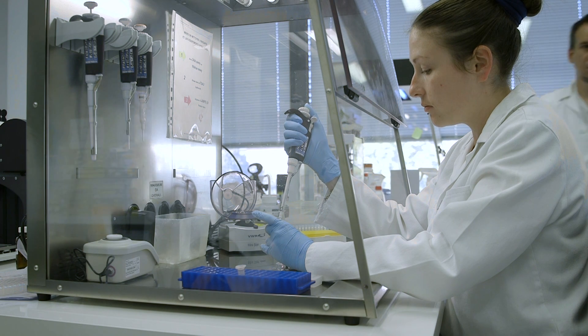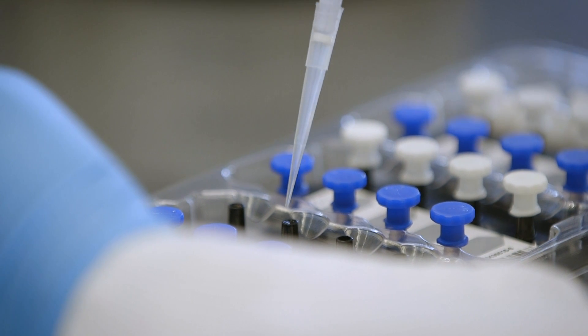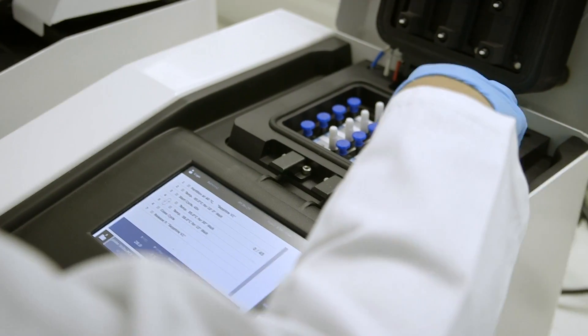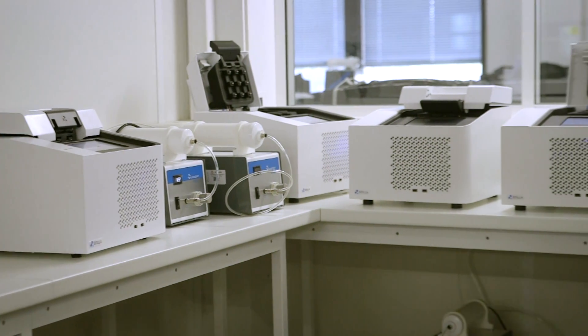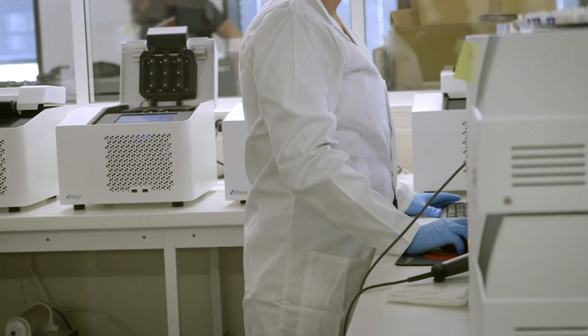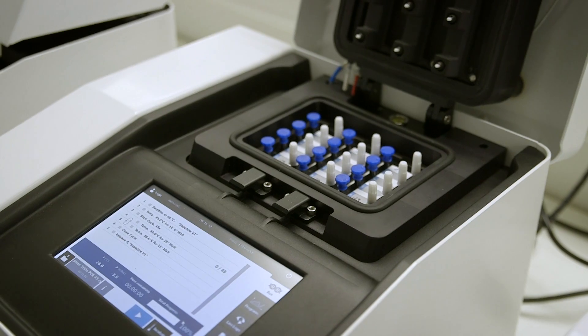We take our consumable oil-filled sapphire chip — our customer simply loads their sample into the chip and then places the chip into our Naica Geode. The Naica Geode is a pressurized thermocycler; it partitions the sample into between 25,000 and 30,000 droplets and then cycles through the desired PCR program.